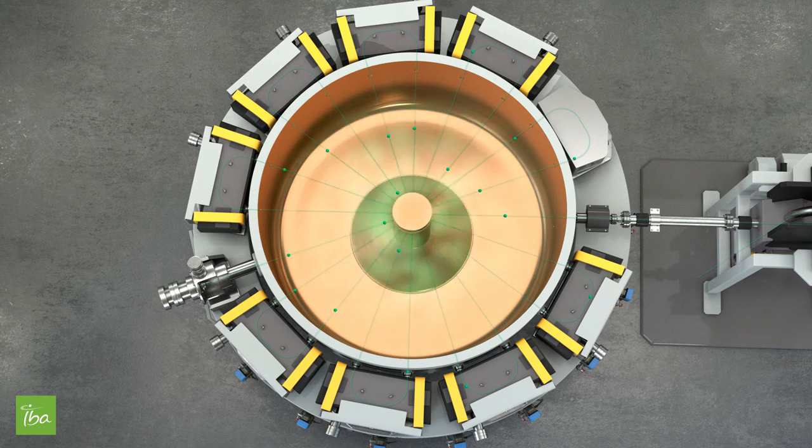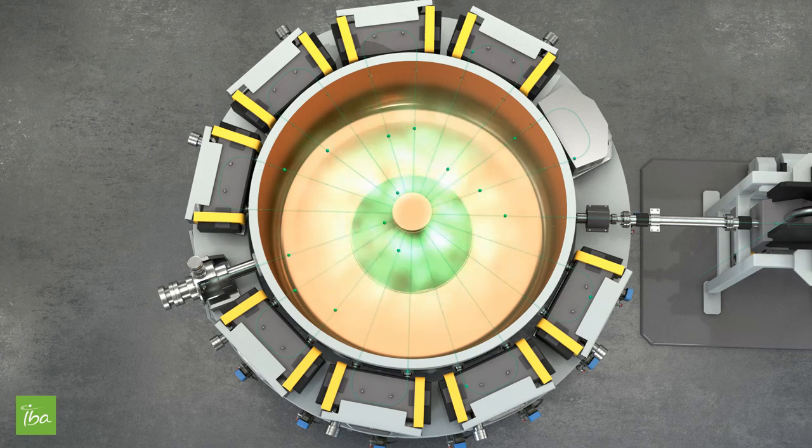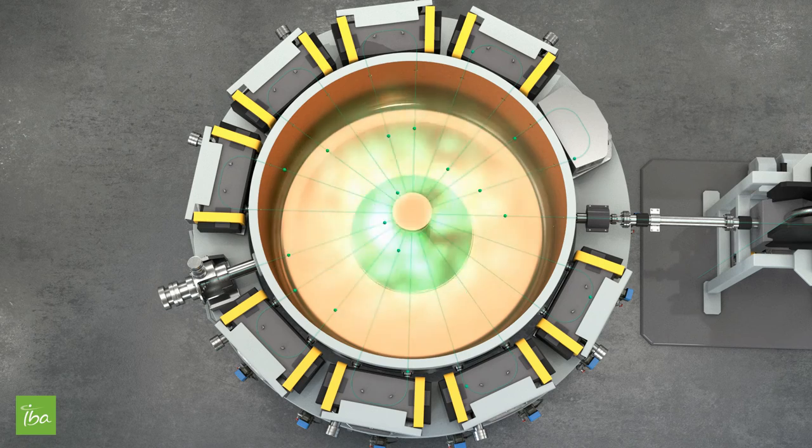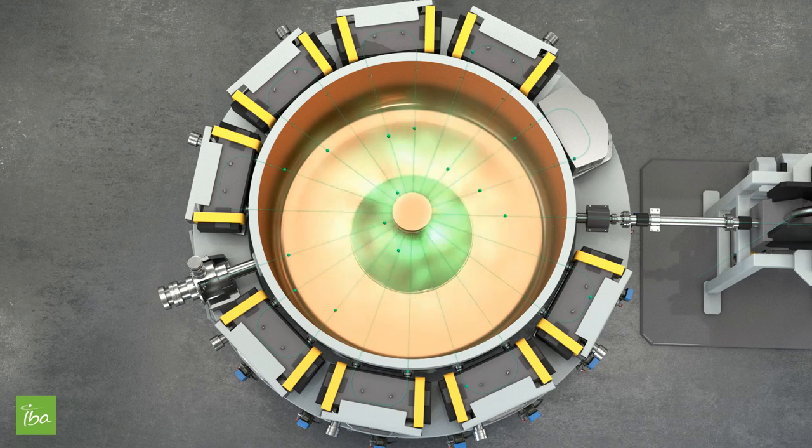After passing through the magnets where they are bent, the electrons are sent back through the cavity. At each pass, they are accelerated by a fraction of the final energy required. When reaching the final energy, the electrons exit the cavity by following their way straight forward through the beam line.